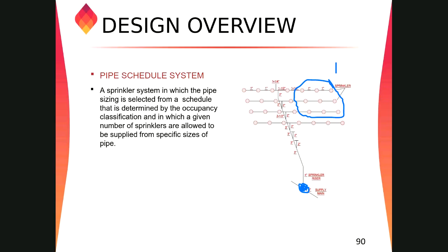Now, if you submit your plan for approval, the general layout drawing, right? And here we have our sprinkler, like this. Those node sprinklers 1, 2, and 3, we have to show these nodes also on our layout drawing to support the consultant who is reviewing the plan.